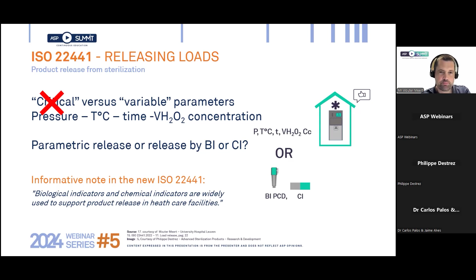And for example, next slide, please. This is how we release loads in our CSSD. This is a param print, and together with the manufacturer of the sterilizer, we looked at all the parameters and decided which parameters are important for us, which have a significant influence on the end result of your sterilization process. These are the ones we have chosen, mostly pressure and the hydrogen peroxide concentration within the process. In this case, this is manually released, and for the moment this is already done electronically within our traceability system. But this is something that is different for all the different kinds of hydrogen peroxide sterilizers.